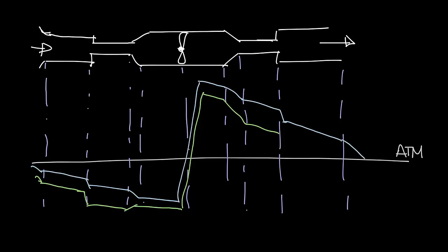And now we have an abrupt change. The velocity decreases. The static pressure will increase. Follows the ductwork and then out into the space. Okay, so let me label these. The green line is static pressure. The blue line on top is the total pressure line. And the difference between these two lines is the velocity pressure.